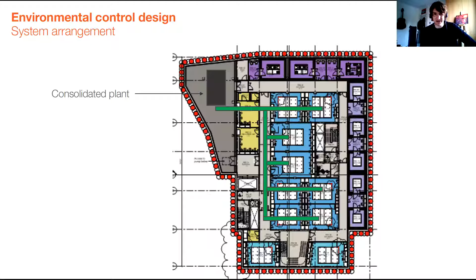So we designed quite a high air volume to go to that experimental box, roughly 80 air changes an hour. And we were going to have a very close control air conditioning system that was just going to maintain the air going to that enclosure at a very stable condition. And so we felt that washing that space with air at a very stable condition would maintain that enclosure at very stable condition. And then the room itself, because there would be people and equipment in there, that room would generate heat, and so the air going to the room would vary depending on how much heat was being gained in the room at the time.